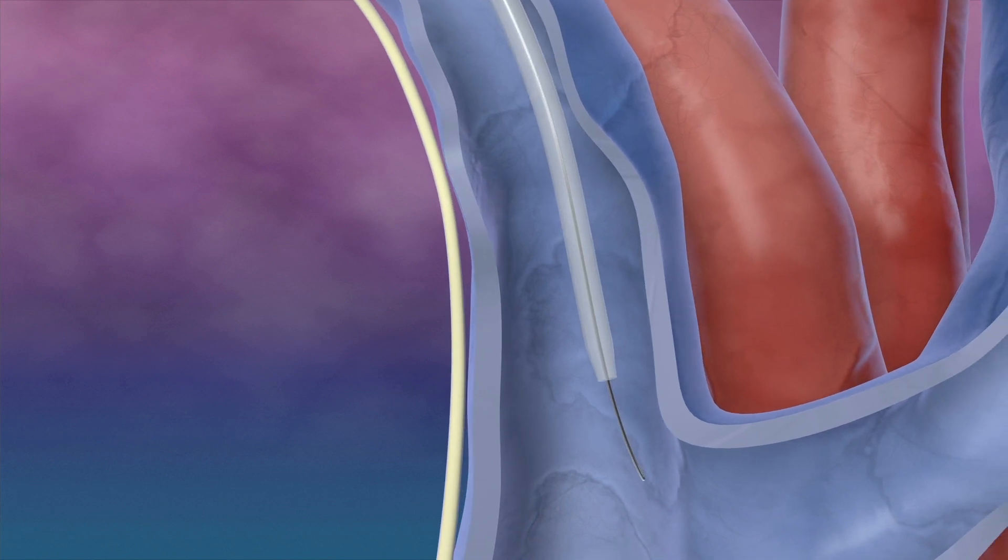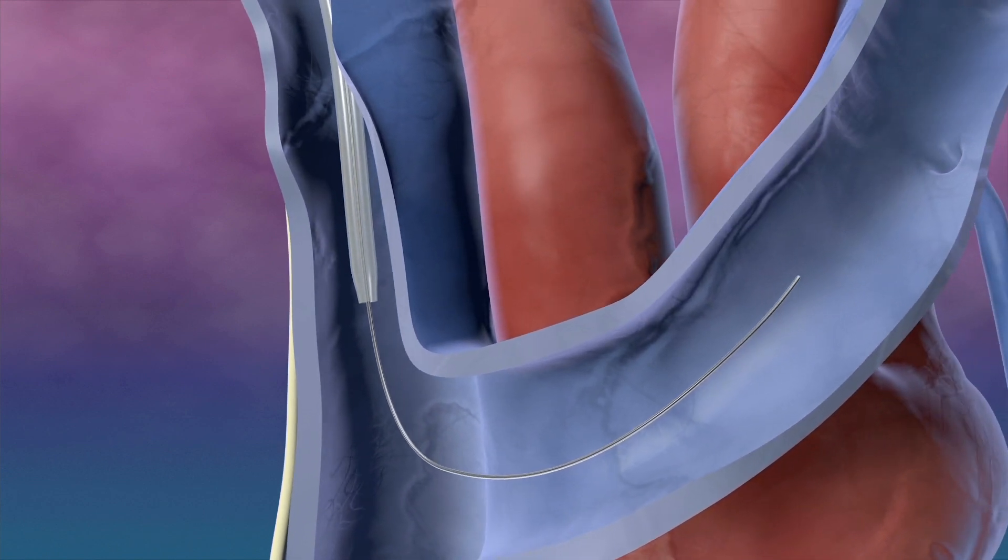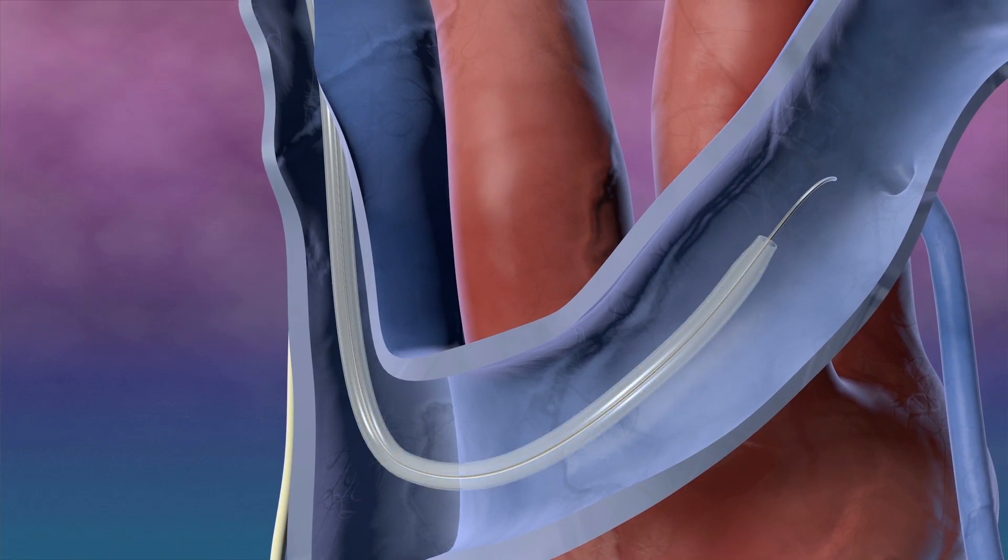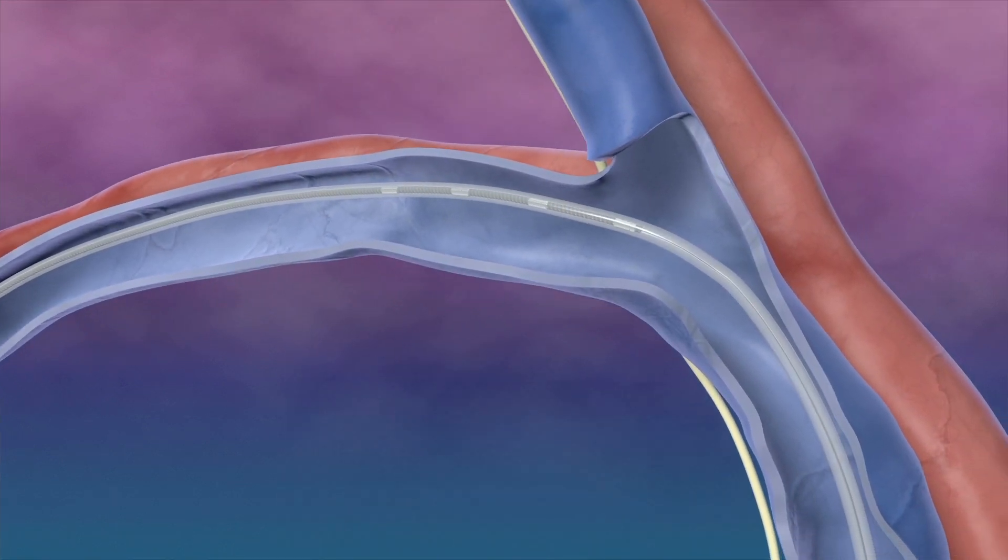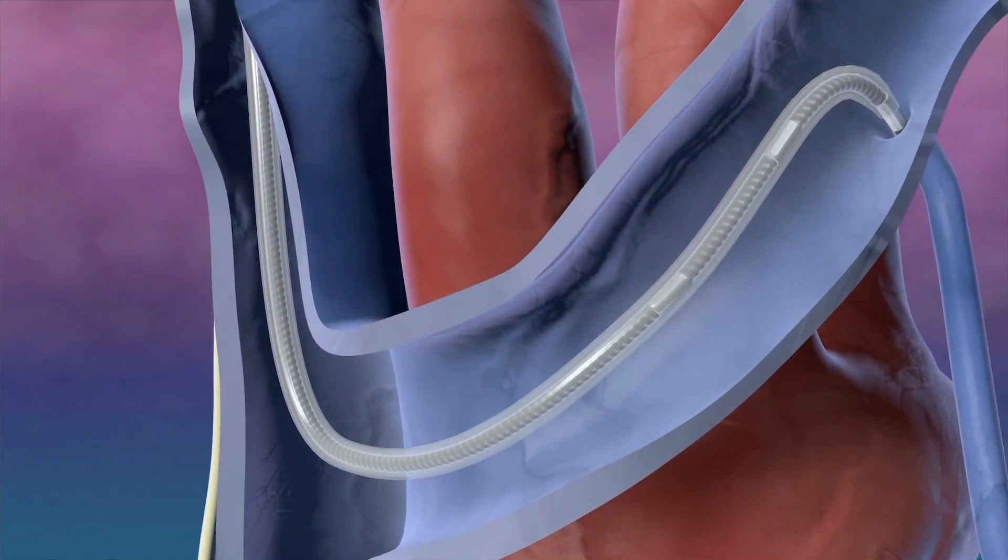The guide wire and catheter are then advanced into the subclavian vein. The guide wire is used to locate the target vessel and then navigated into the target vein. The left stimulation lead is deployed over the wire into the vein and positioned at the level of the left atrium.